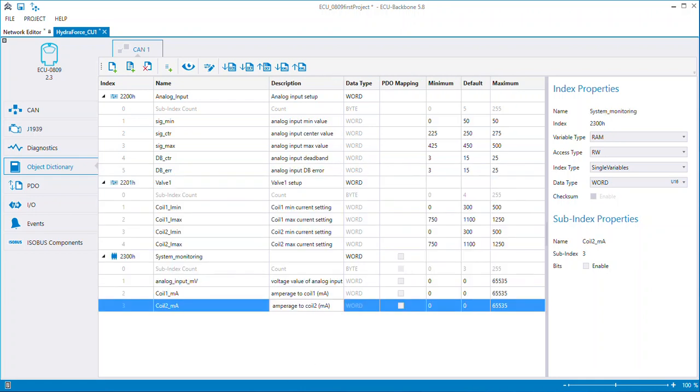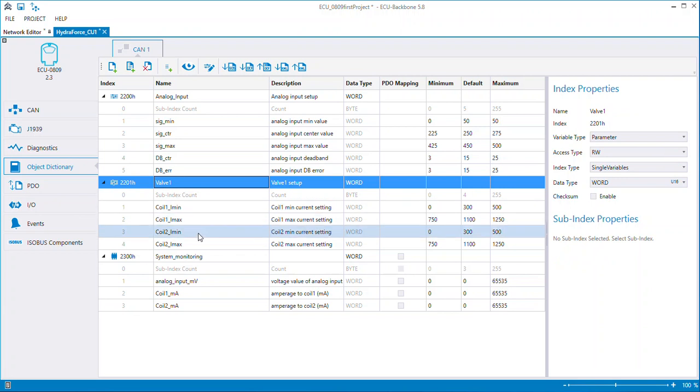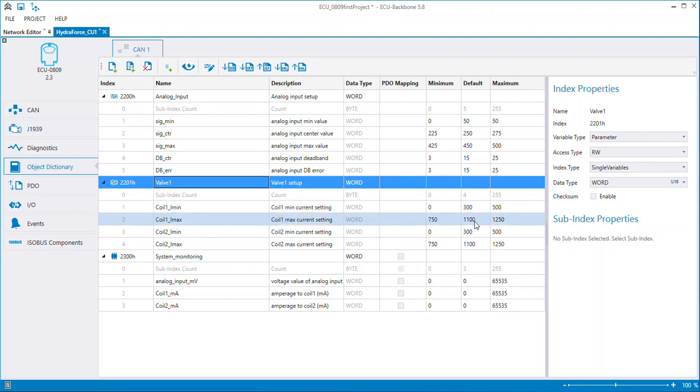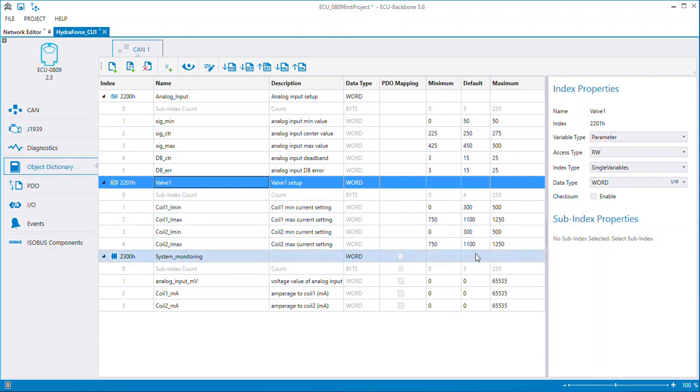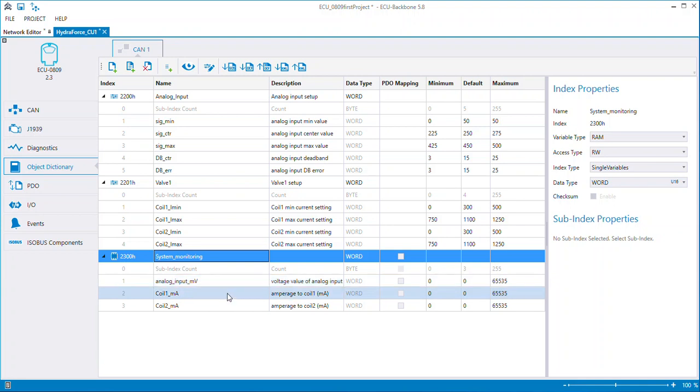I have added two more indexes. I added valve one that has a valve one setup. It's a word also, also a parameter. There are four sub-indexes in it. Coil one I min and I max, Coil two I min and I max. And I've set up some initial values. So the minimum current going to the coil could be 300, maximum being 1100. And there's some variances in there also. And the same thing for coil two. Then I added a third index that is of RAM. So I select it and you see it's a RAM over here. We're going to be able to monitor through our service tool the voltage value of the analog input and then the amperage going to coil one and coil two.